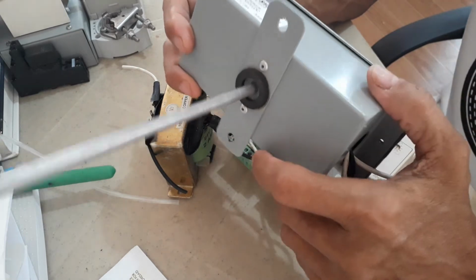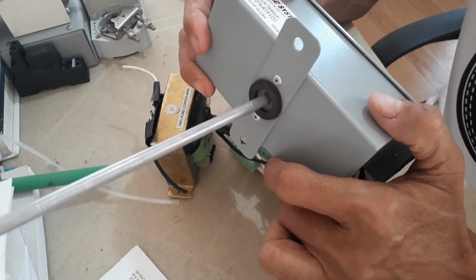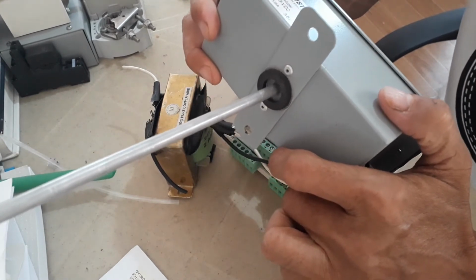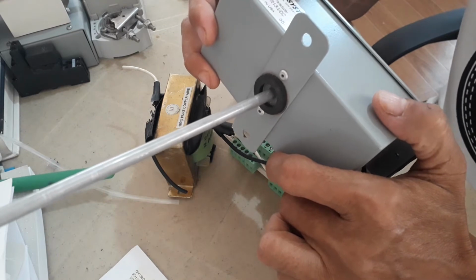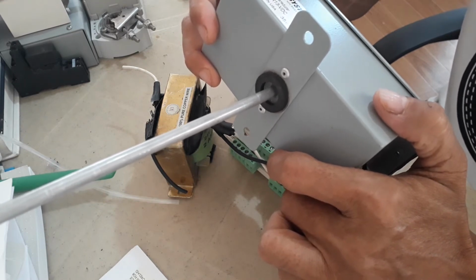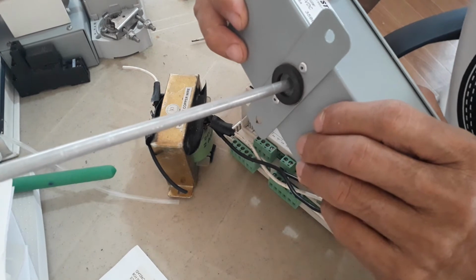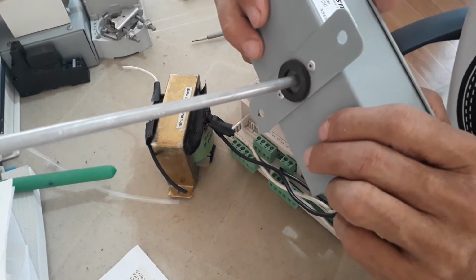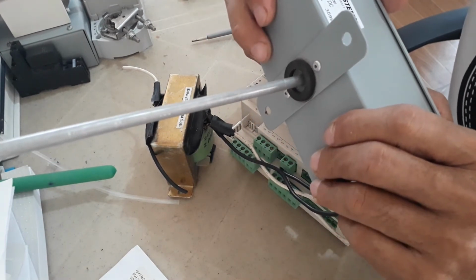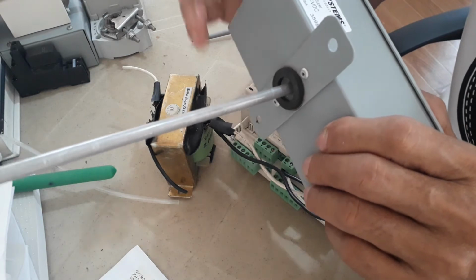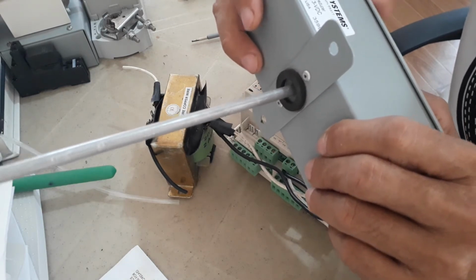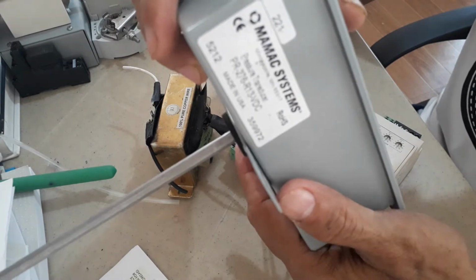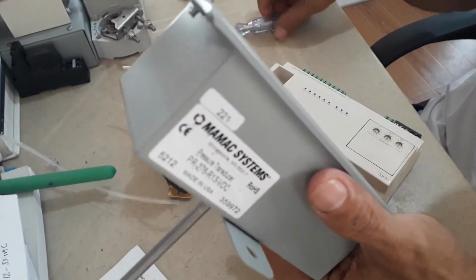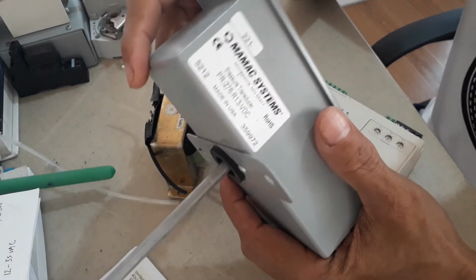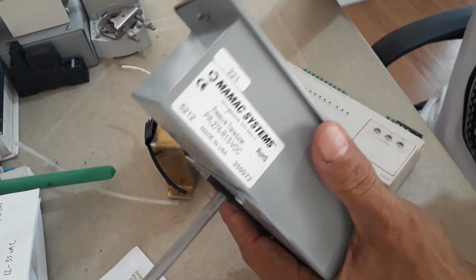Now we use this also in staircase pressurization because our air supply is coming from the duct. So I use one of these to prevent high pressure in the duct, so I can open my relief damper. We are using this duct pressure transducer. Okay, so this is a pressure transducer. This is not differential pressure. This is a static pressure transducer.